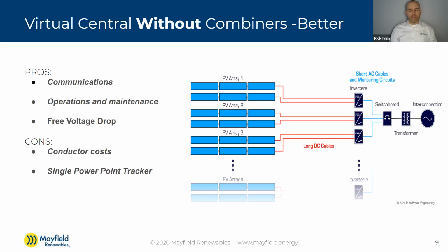Yeah. So when you have that debate, do I go with the virtual central with string inverters versus an actual central inverter? Over the last 5 years, that argument keeps changing. Five years ago you would say anything above a megawatt should still be central, and then a year later, anything above 1.5 should be a true central. And now you're getting up around 2, 3 or 4 megawatt blocks where you're saying string inverters are now better for that. So that line between using string inverters in a virtual central versus an actual central keeps going up in size for those megawatt blocks.